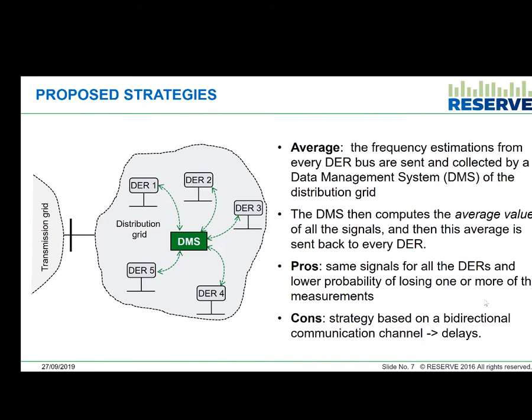The third and last strategy is called the average strategy. The frequency estimation is made locally at every point, then sent to the data management system, where the average of all points is calculated. This average is then sent to the controller of every plant. The positive aspect is the use of only one signal for all the sources. The drawback is that the strategy is based on bidirectional communication — sending first to the DMS and then back to the sources — so the delay is higher.